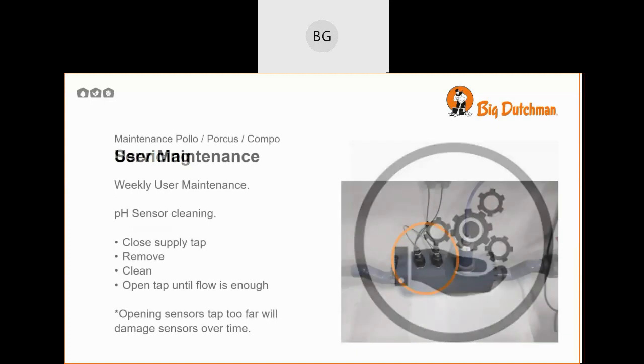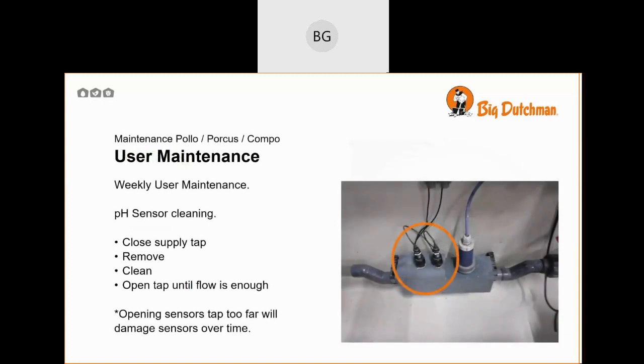Servicing. User maintenance. Weekly user maintenance includes cleaning the pH sensors: close the supply tap, remove the pH sensor, clean it gently, and once reinstalled, open the tap until the flow is enough. This can be seen in a sight glass just to the left of the picture. Once the pipe is running full, that is sufficient flow. It doesn't need to be any more than that. Opening the sensor tap too far will damage the sensors over time, and they will not last the 12 months that we allow for them.